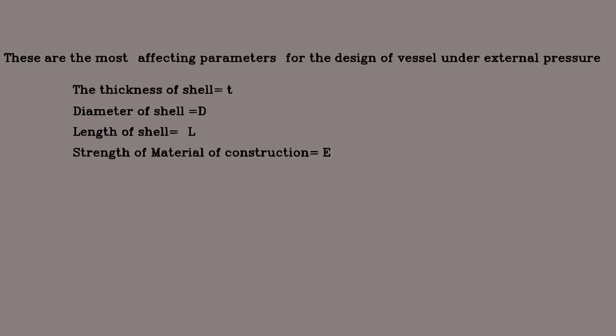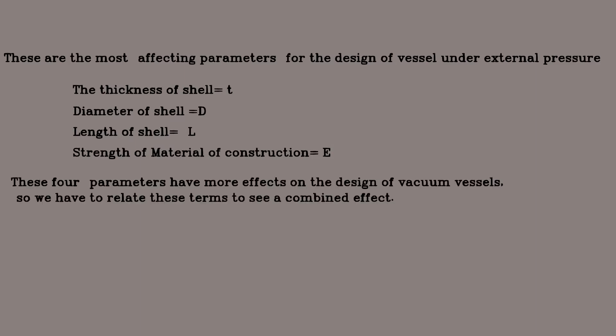For the design of external pressure vessels, the most affecting parameters are: the thickness of shell T, the diameter of shell D, the length of shell L, and the elastic modulus of the material of construction E. These four parameters have the most effect on the design of vacuum vessels, and we need to relate these terms to see their combined effect.